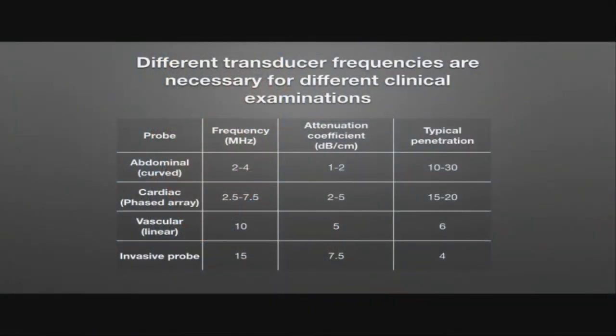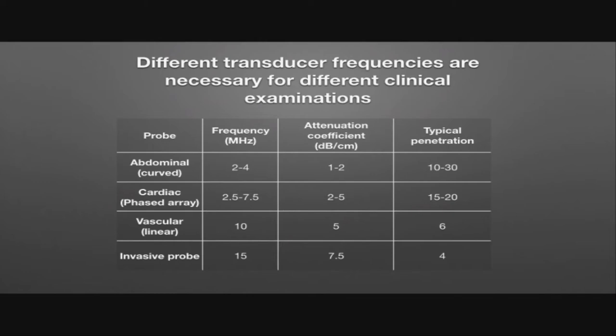The different transducers we mainly deal with include abdominal probes, typically operating at 2 to 4 MHz, with an attenuation coefficient of around 1 to 2 dB/cm and typical penetration of 10 to 30 cm. Next up the frequency ladder are the phased array or cardiac probes, operating at 2.5 to 7.5 MHz, with an attenuation coefficient of 2 to 5 dB/cm and typical penetration of 15 to 20 cm.